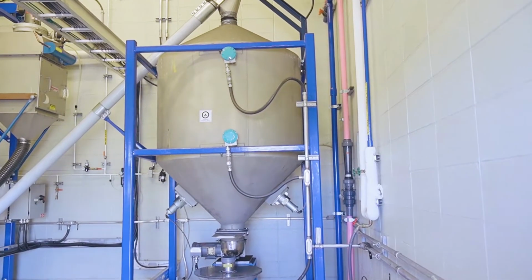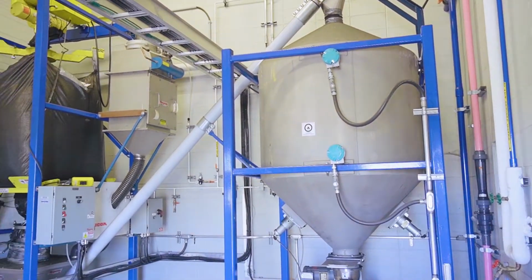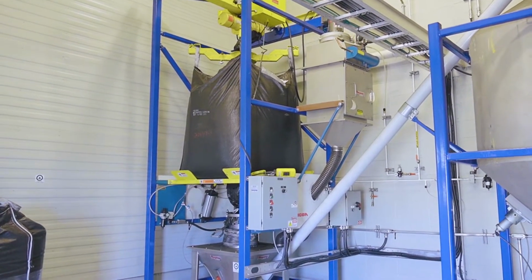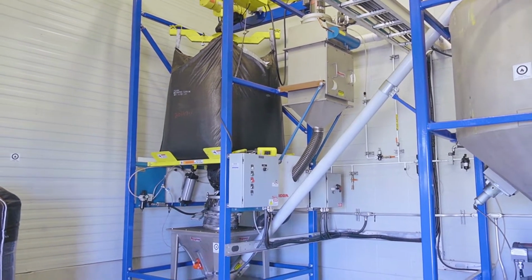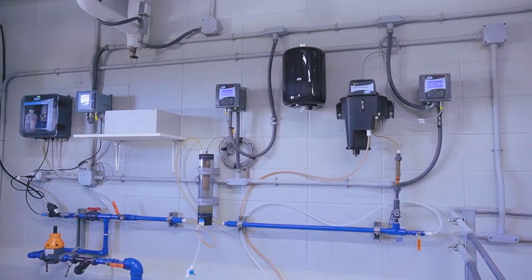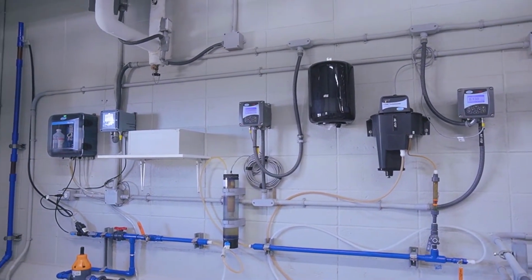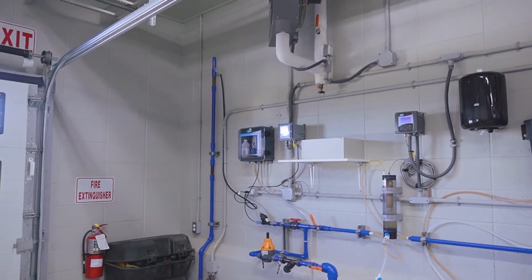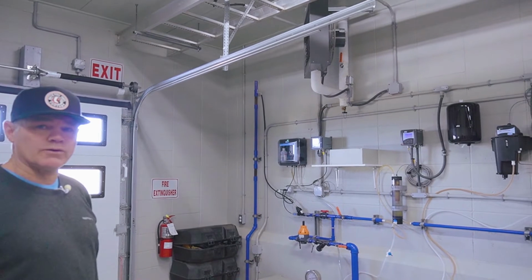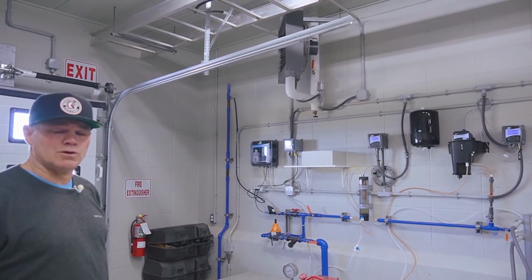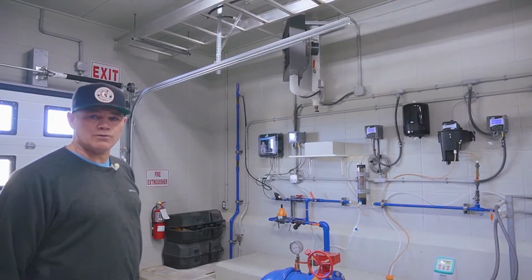So this is the PAC room. We use powder activated carbon to remove taste and odor in the water. This is a tree-based powder activated carbon rather than a coal-based one, because a coal-based powder activated carbon would foul our membranes and we can't use it. So basically it's burnt trees. We have an online turbidity meter, online pH meter, and online chlorine analyzer. Alberta Environment gives us a certain set point for free chlorine, but we try and keep the free chlorine in Claresholm as low as possible. The lower the chlorine leaving the water plant, the better.